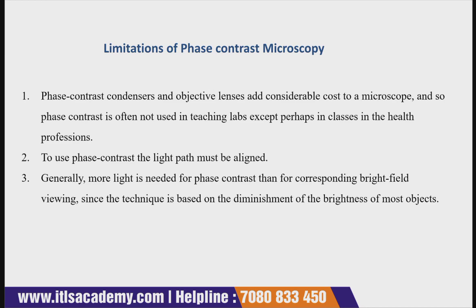The limitations of phase contrast microscopy are: phase contrast condensers and objective lenses add considerable cost to the microscope, so it is often not used in teaching labs except in health profession classes; the light path must be aligned for phase contrast, which is another limitation; and generally more light is needed for phase contrast than for corresponding bright-field viewing, since the technique is based on diminishment of the brightness of most objects.